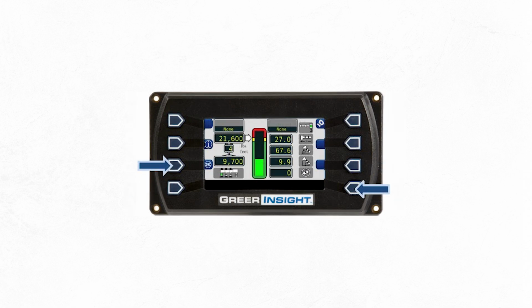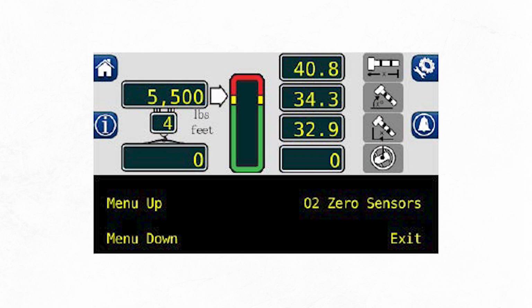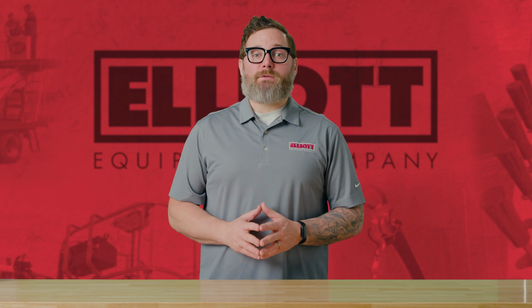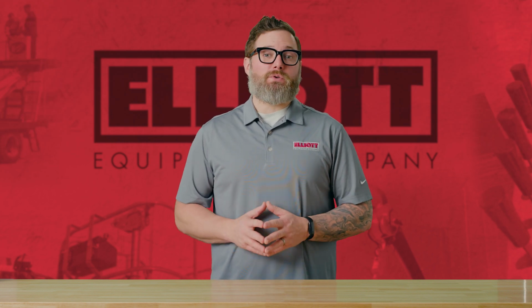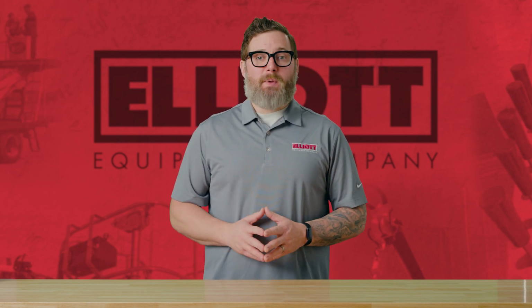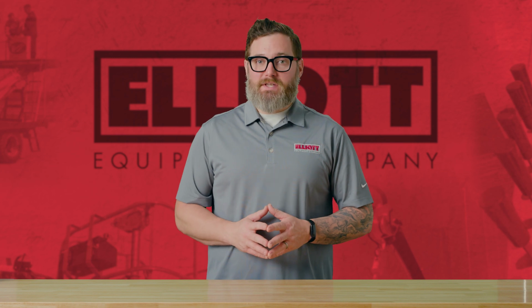If you don't see the calibration button, press and hold the indicated button simultaneously until you get a prompt for the security code. Once the security code has been entered, the display will show this menu. Scroll through the menu options by pressing the menu up or menu down buttons. To select an item, just press the button next to the menu listing. Now, the main menu items used to calibrate the system are 02 0 sensors, 03 span sensors, and 04 swing sensors.